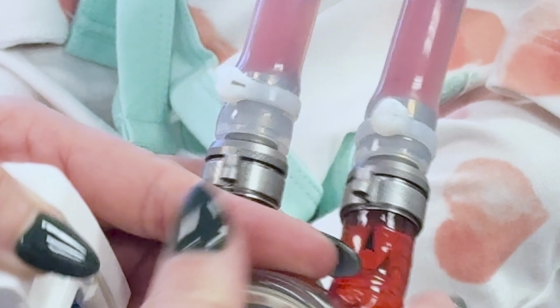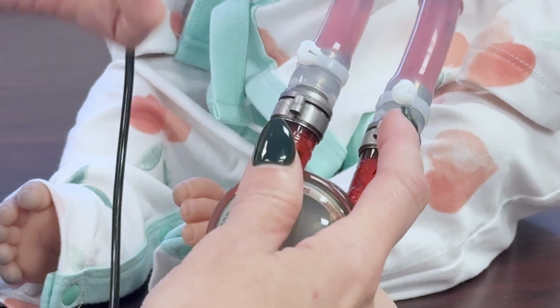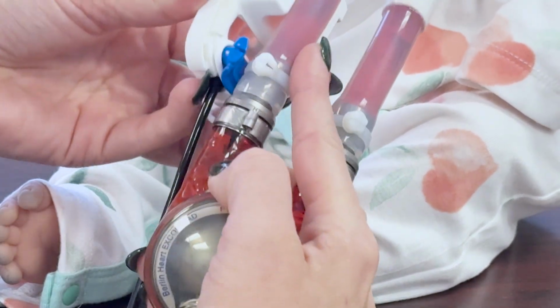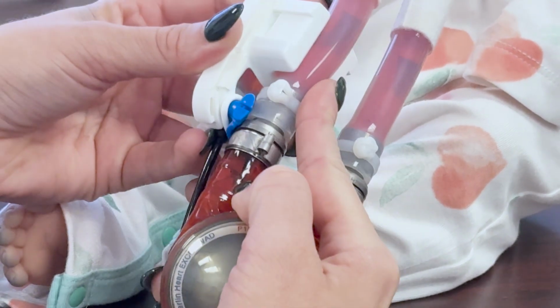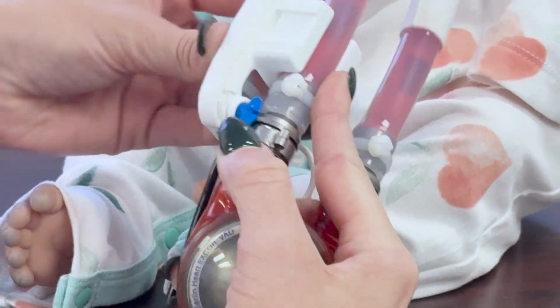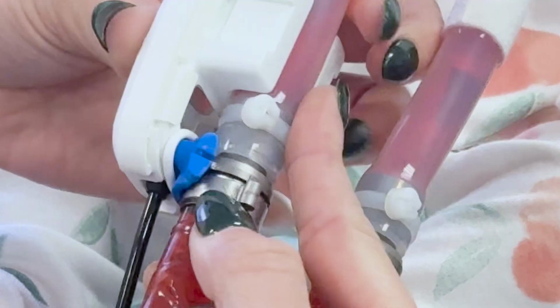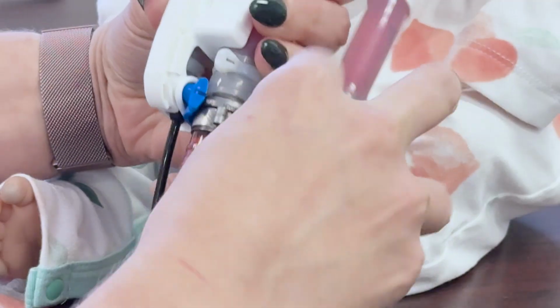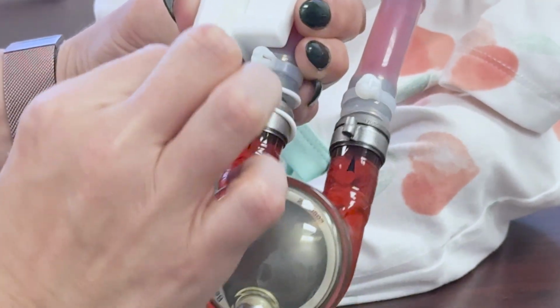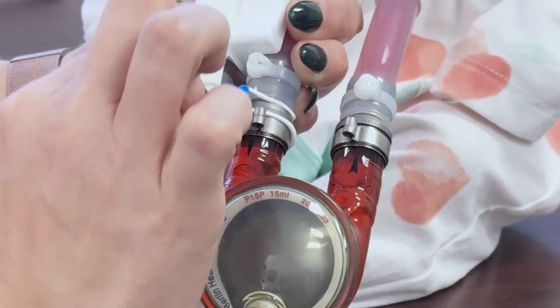What I like to do to really ensure connection is place the flow sensor a little up on the cannula, then carefully slide it down until the plastic ledge sits firmly on top of the titanium ledge. There should be resistance if you try to slide it any further. Now you'll secure your quick clip either above, below, or around the zip tie.